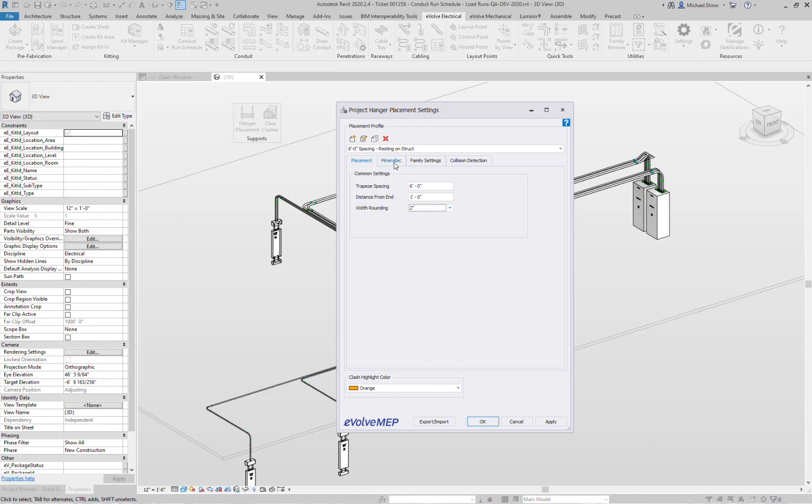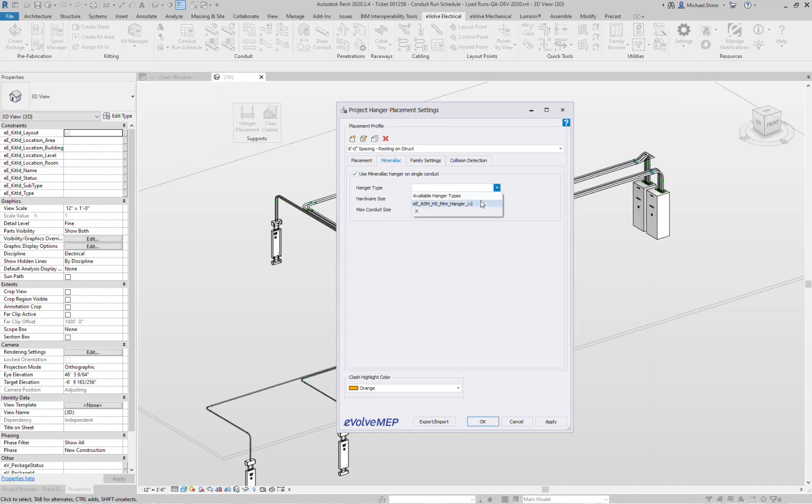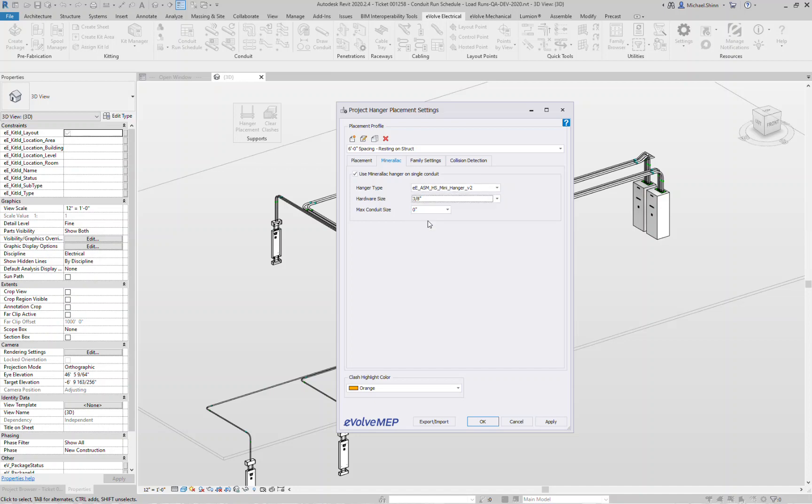Next we have our mineral act tab. With eVolve 5.0 we now have the ability to automatically place Minerallac hangers with our hanger placement command. Previously it was just trapeze only. What is your hardware size? Three eighths. And then what is the maximum conduit size for your Minerallac hangers? I'll just grab three inches for the time being. So if it gets greater than three inches they'll then revert it back to a trapeze for that single hanger.